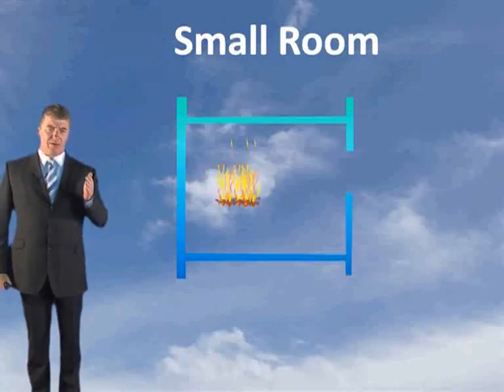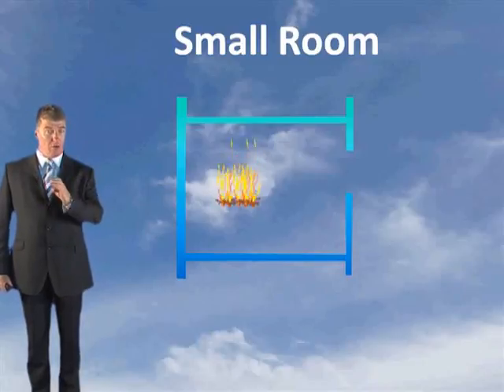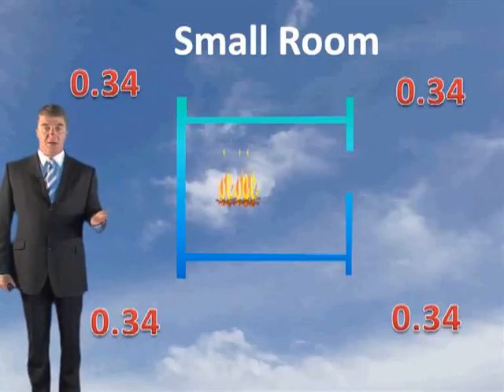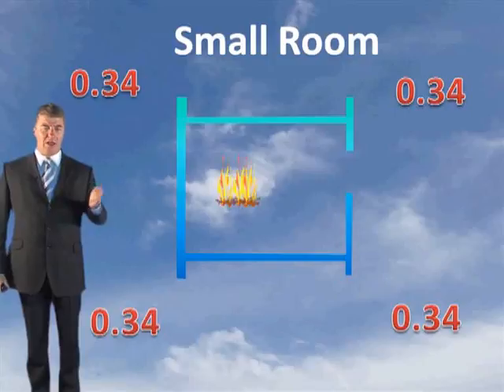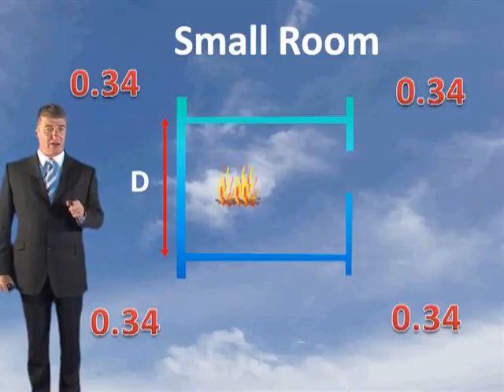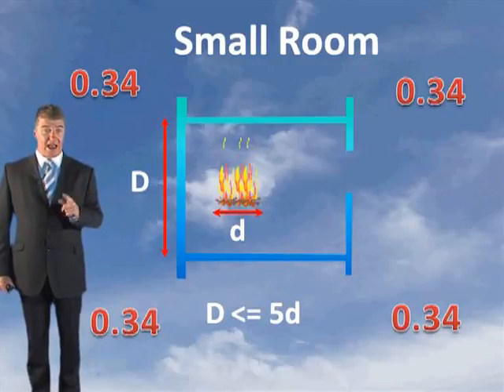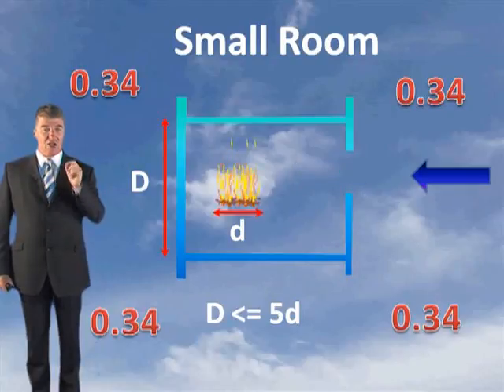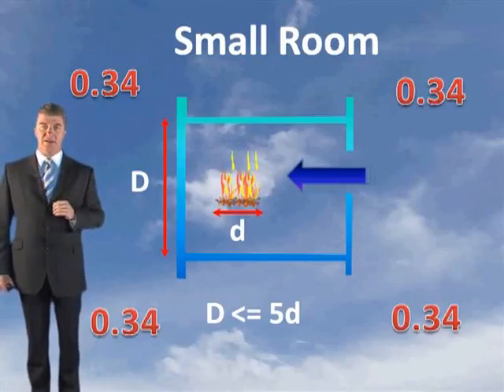There are three coefficient options: 0.19, 0.21, or 0.34. If it's classified as a small room, you use 0.34. A room is considered small when the maximum room dimension is less than or equal to 5 times the diameter of the design fire size, and air can only come in from one direction. In this case, we're not using 0.34 because air can come in from more than one entrance.